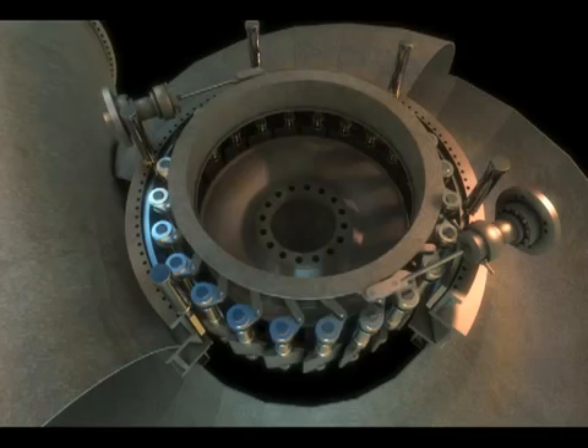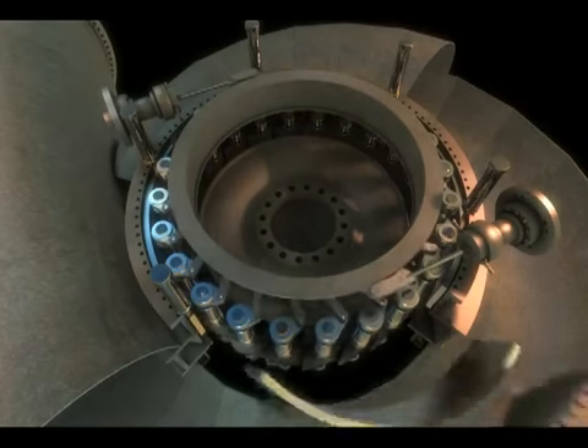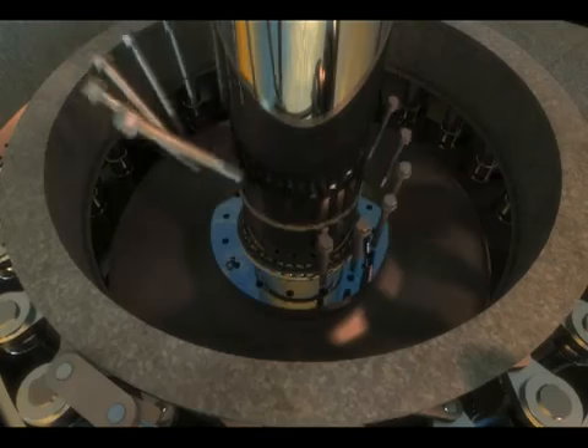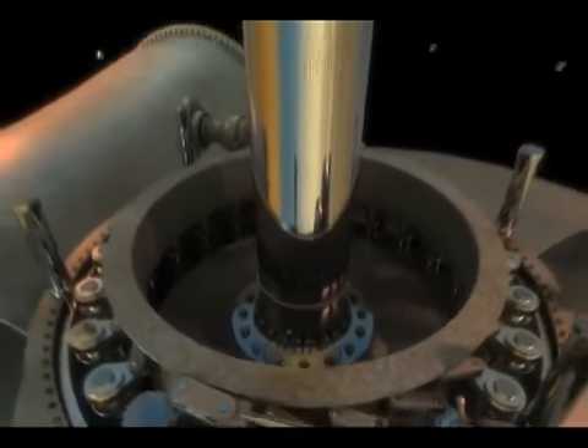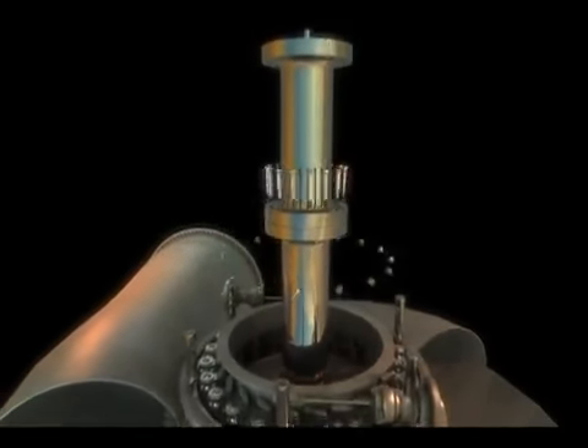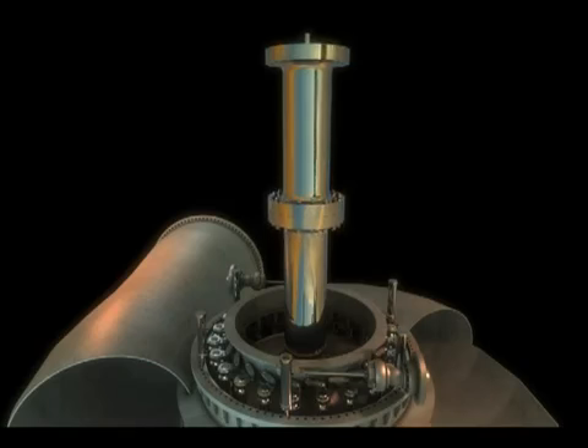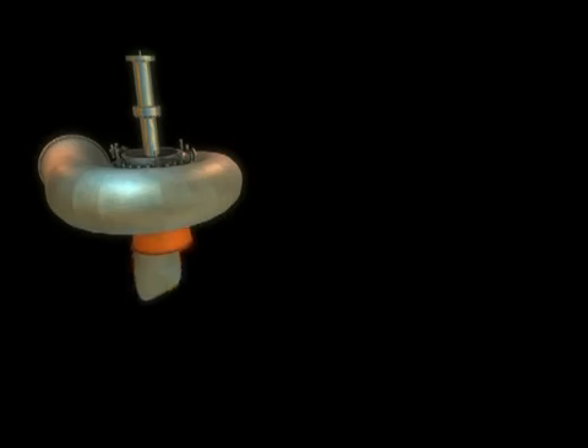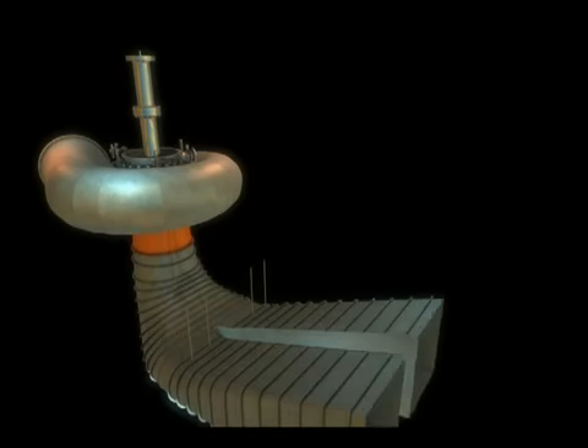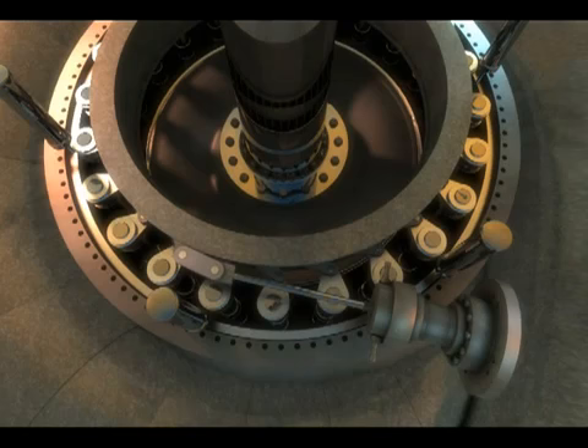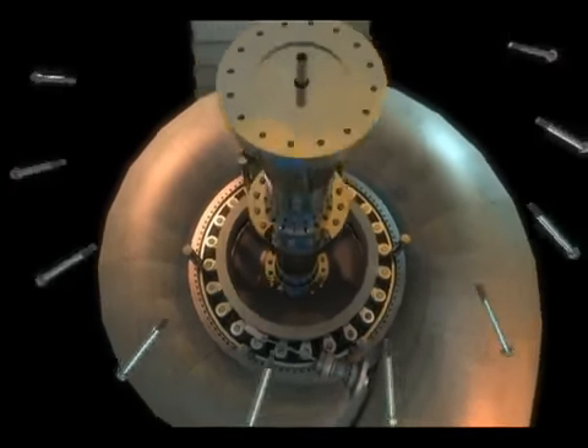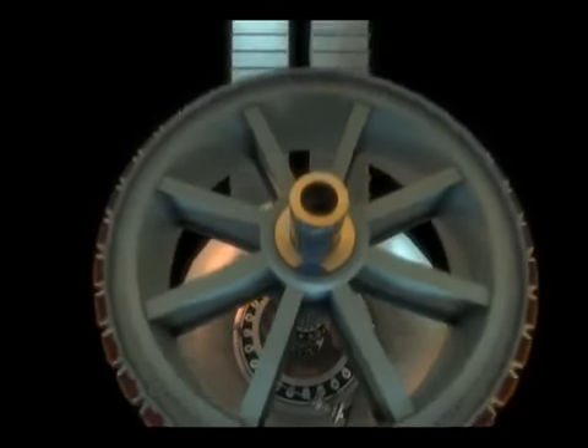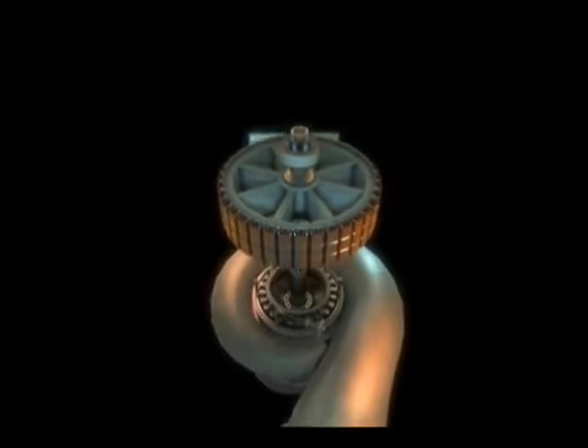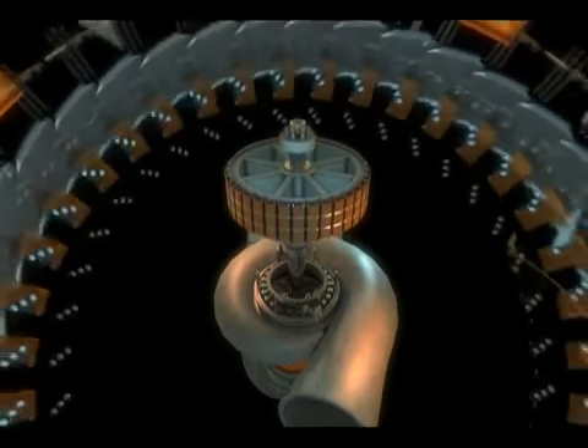The movable blades and their hydraulic operating system. The speed regulator. The turbine runner that turns with a vertical shaft that has a guide bushing to avoid eccentricity and that is attached to the lower shaft of the generator. The draft tunnels, which carry the water to the oscillation cavern once the energy generation process is complete. The generator is mounted above the turbine's vertical shaft. Generator parts include the rotor, the excitation system and the stator.